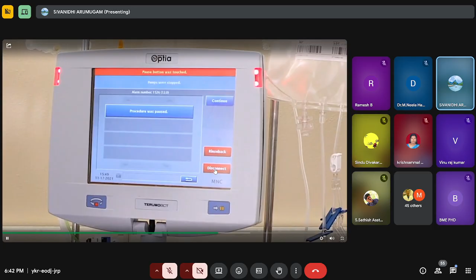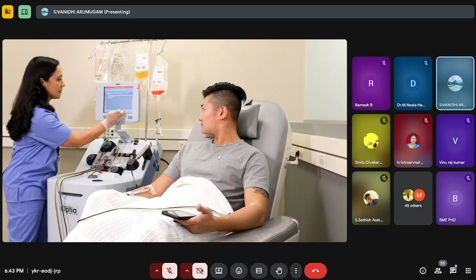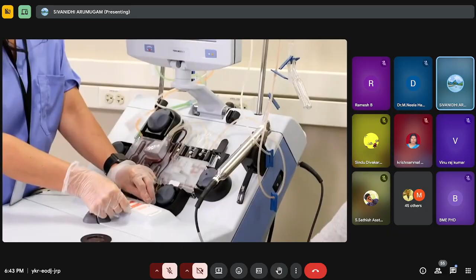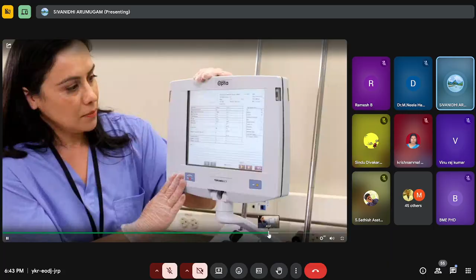The system allows operators to easily troubleshoot and optimize procedures. If the system detects an operation error or a potentially unsafe operating condition, it triggers an alarm. The alarm screen shows all the possible causes of the alarm. The system may stop the pumps or the centrifuge. The operators can customize each procedure by entering run targets. The system also returns 100% of the blood remaining in the set back to the patient.